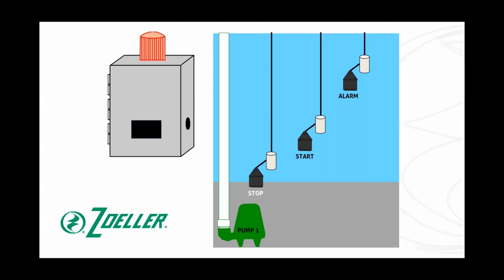So think about it. If we flip-flopped or switched the location of our stop float and our start float, what would happen? Like I said, it will still operate. The pump's going to come on, but in a situation like this, it's only going to operate the pump based off the movement of one float switch. Therefore, it's going to short cycle your pump. Like I said, this is a common mistake that we see, and unfortunately, it generally leads to a premature pump failure.